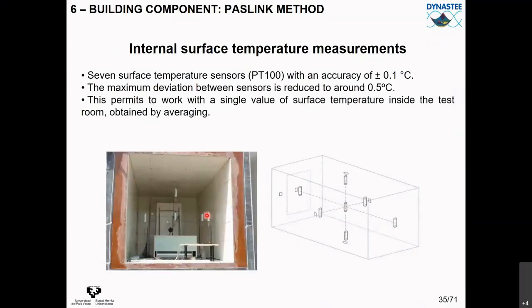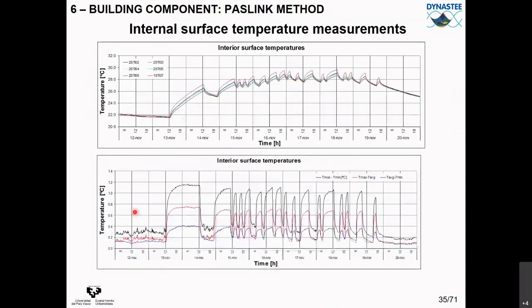A thermoresistance is usually called PT100 because it is made of platinum wire that has an electrical resistance of 100 ohms at 0°C. What you actually measure are the ohms — the higher the temperature, the higher the electrical resistance — and you convert that to temperature. This is why they are called thermoresistances. In the test box, surface temperatures are also measured at many points — east, west, ceiling, floor, north. The variability of surface temperatures can be much higher: even with 0.1°C sensor accuracy, maximum minus minimum can reach 1.1°C, so you must be careful when using surface temperature in your models.